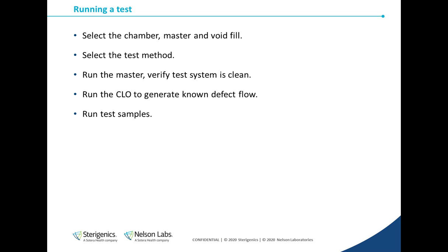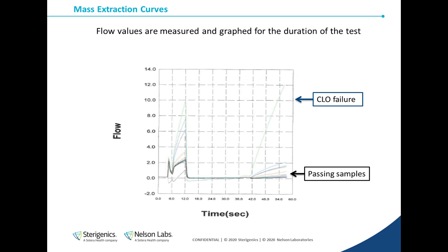Next, we run the CLO to determine a final flow value for a 2 micron or a 5 micron leak. Again, the leak size depends on the method. The vial method is validated for a 2 micron leak, so we would run the 2 micron CLO. And finally, we would run all the test samples.